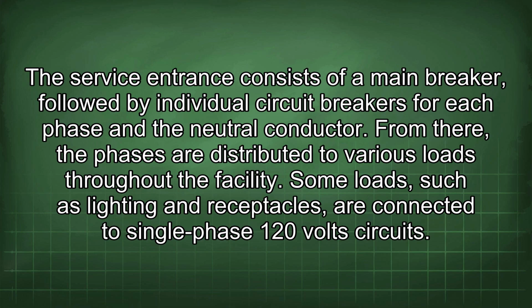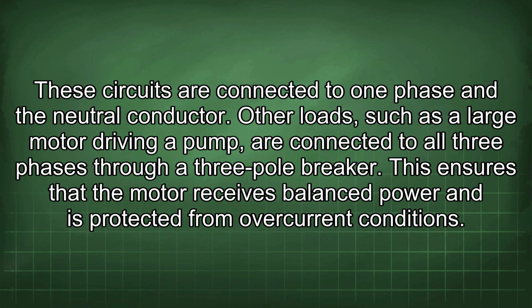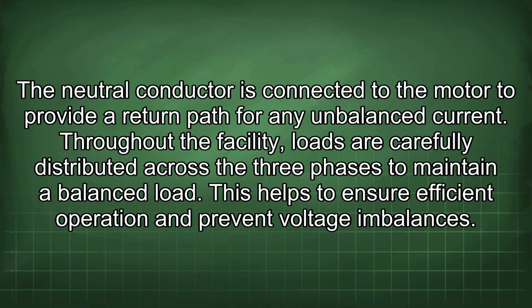Some loads, such as lighting and receptacles, are connected to single-phase 120-volt circuits. These circuits are connected to one phase and the neutral conductor. Other loads, such as a large motor driving a pump, are connected to all three phases through a three-pole breaker. This ensures that the motor receives balanced power and is protected from overcurrent conditions. The neutral conductor is connected to the motor to provide a return path for any unbalanced current. Throughout the facility, loads are carefully distributed across the three phases to maintain a balanced load. This helps to ensure efficient operation and prevent voltage imbalances.